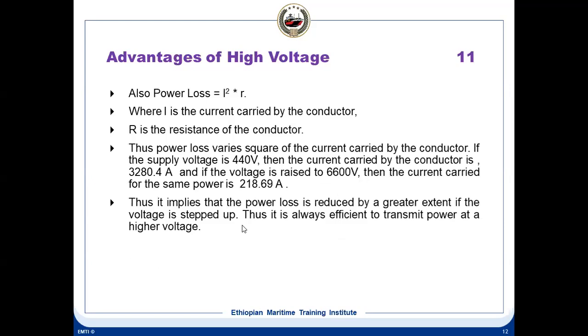Also the copper losses: power loss is I square R, where I is the current carried by the conductor and R is the resistance of the conductor. So power loss varies as the square of the current carried by the conductor. If the supply voltage is 440 volt, the current carried by the conductor is 3280. If the voltage is raised to 6600 volt, the current carried for the same power is 218.69 amps. You can see the difference in the current: almost 3280 changes to 218.69 amps. So the power loss is reduced to a greater extent if the voltage is stepped up. Thus, it is always efficient to transmit power at a higher voltage.